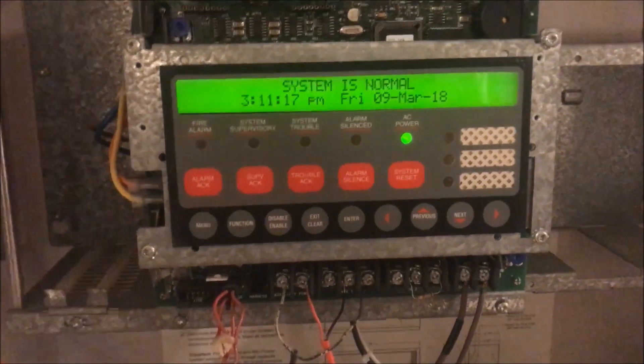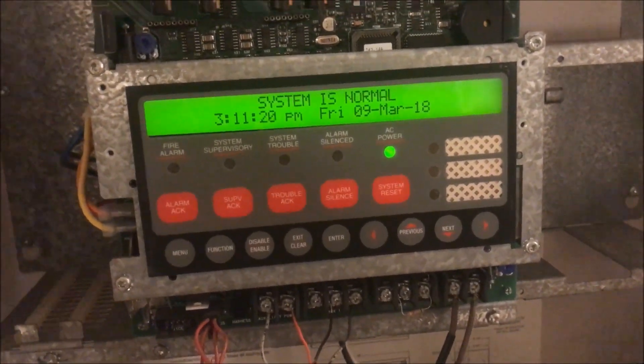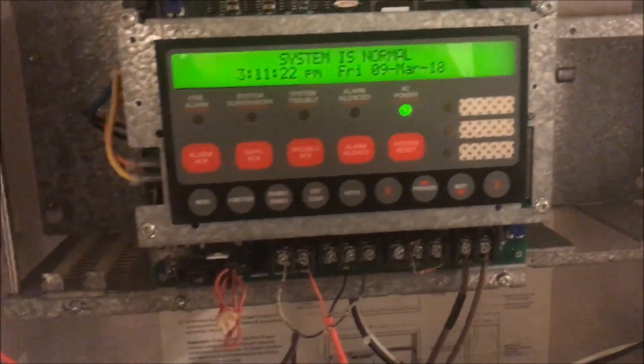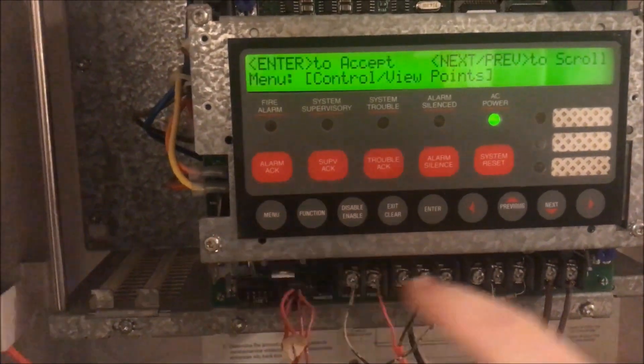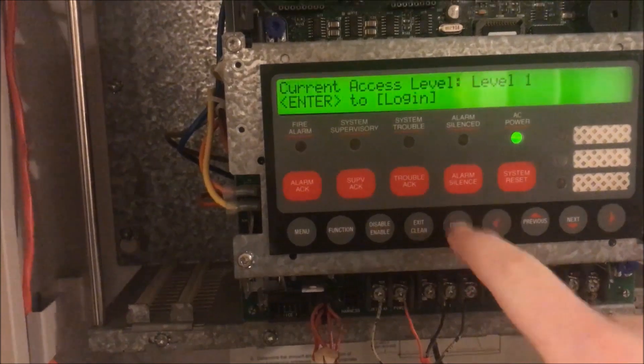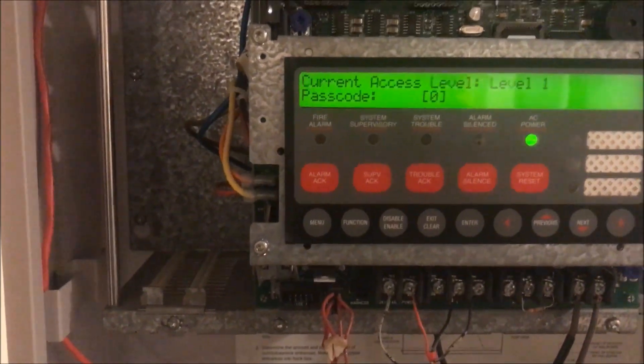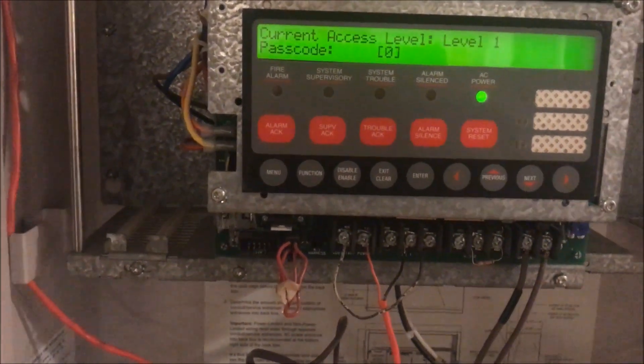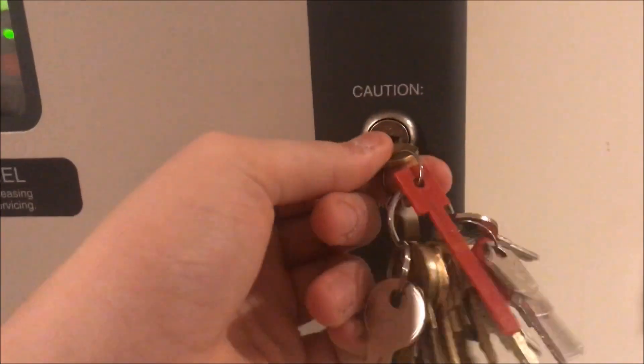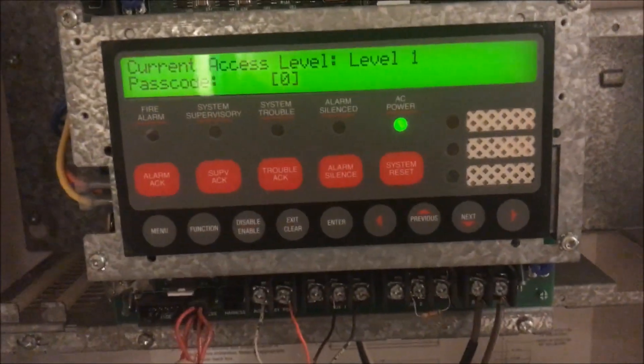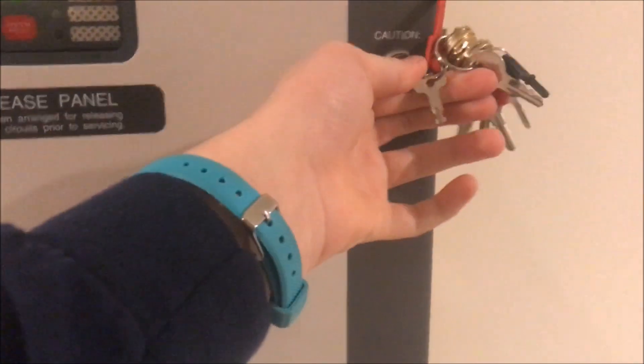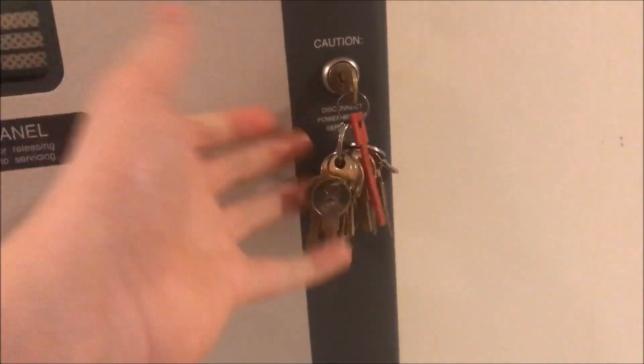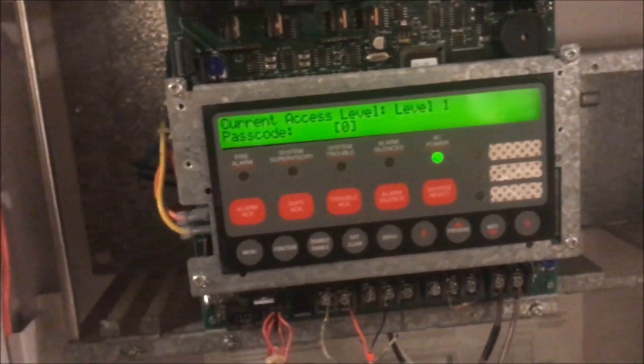Simplex uses a system of levels to control different access within the panel. Each level is passcode protected, so you need a different passcode to get into each level — except for level one. Level one requires no passcode; it just needs some way of getting into the panel, whether that's a B key opening the door or a B key in an annunciator. You basically just need a B key.